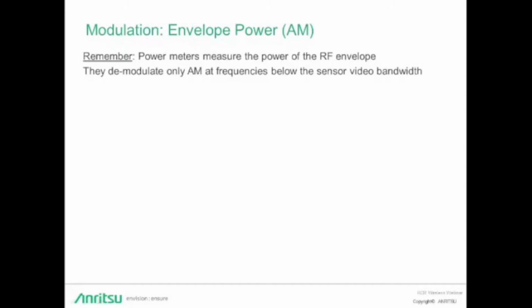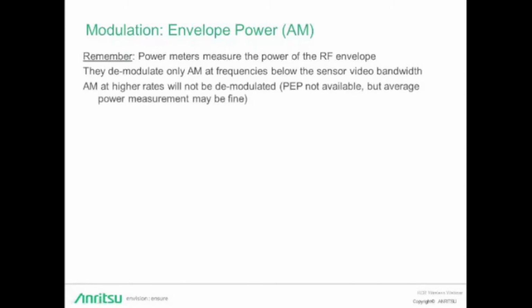So here are a couple of points to keep in mind. Remember what we talked about, that the power meter measures the power of the RF envelope. So in essence, they demodulate only AM at frequencies below the sensor video bandwidth. AM at higher rates will not be demodulated, meaning that the peak envelope power will not be available. Now, depending on the sensor, your average power might still be fine.